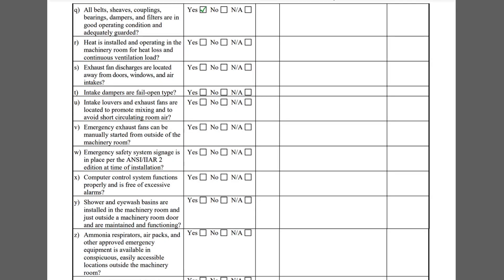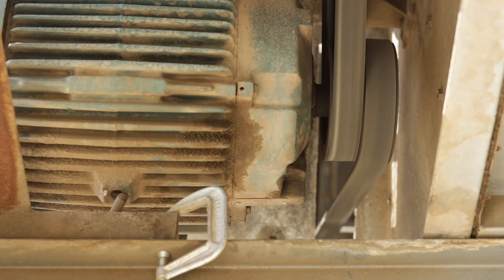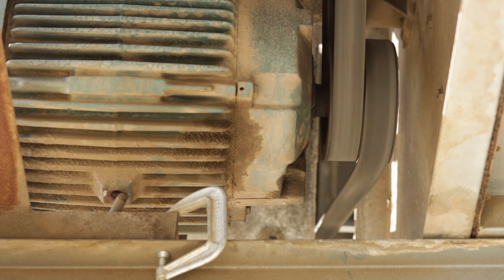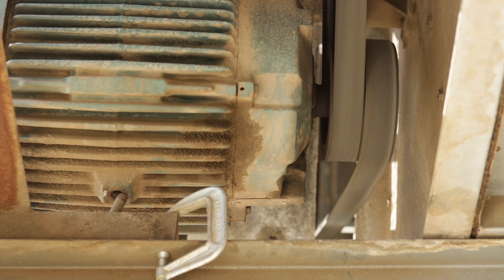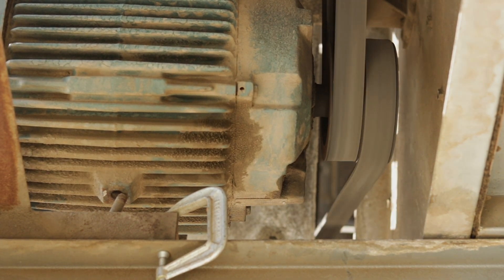Item Q pertains to the belts, sheaves, couplings, bearings, dampers, and filters associated with the ventilation system equipment. It is important to check that all rotating components are properly guarded to protect employees from injury.